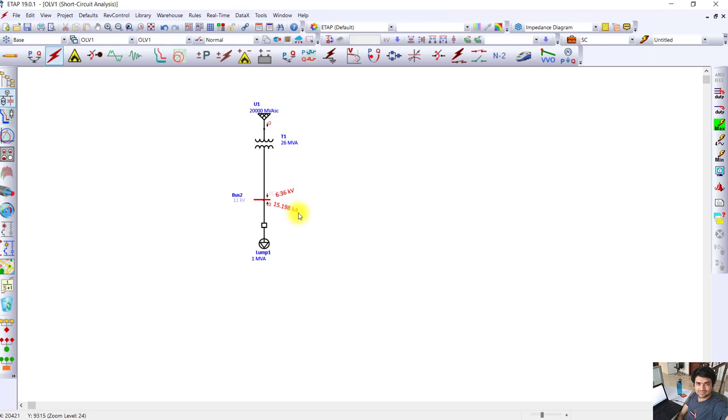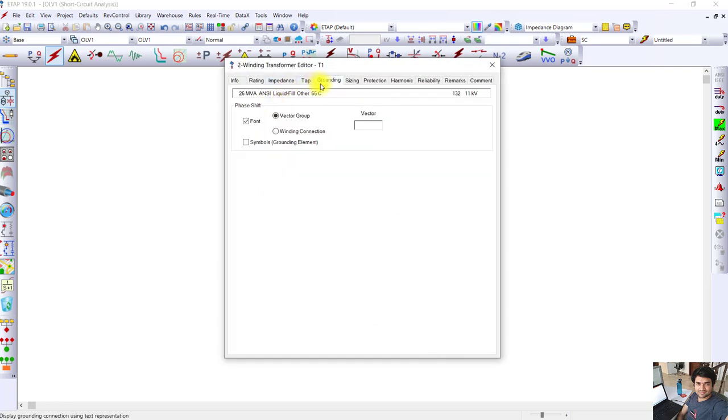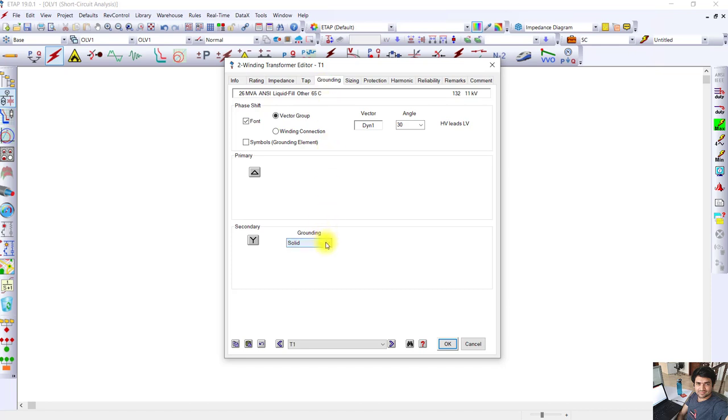It's depreciating the life of transformers, conductors, and also the earthing system. As current passes through the earthing system, corrosion is taking place in the earthing rods. We want to limit this. So let's connect some impedance here. I will select resistor instead of solidly ground.